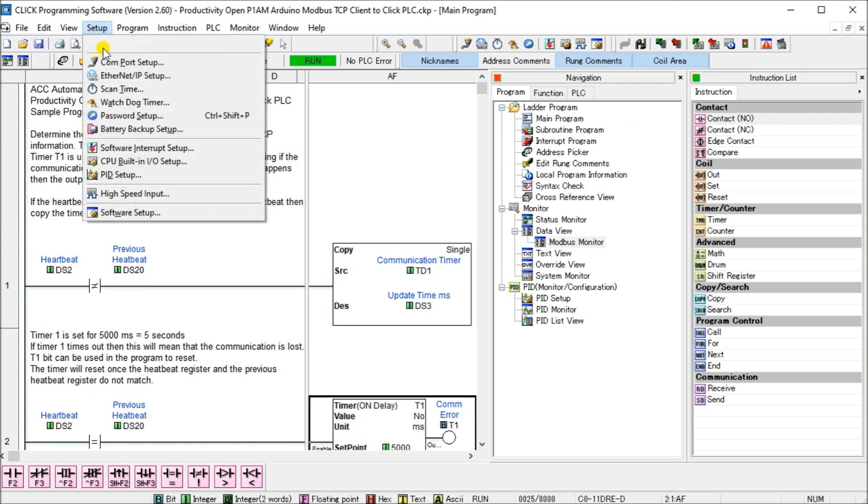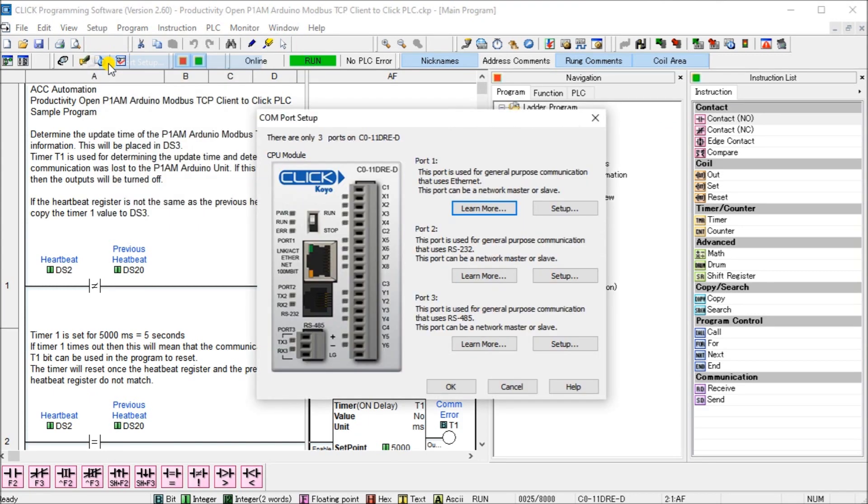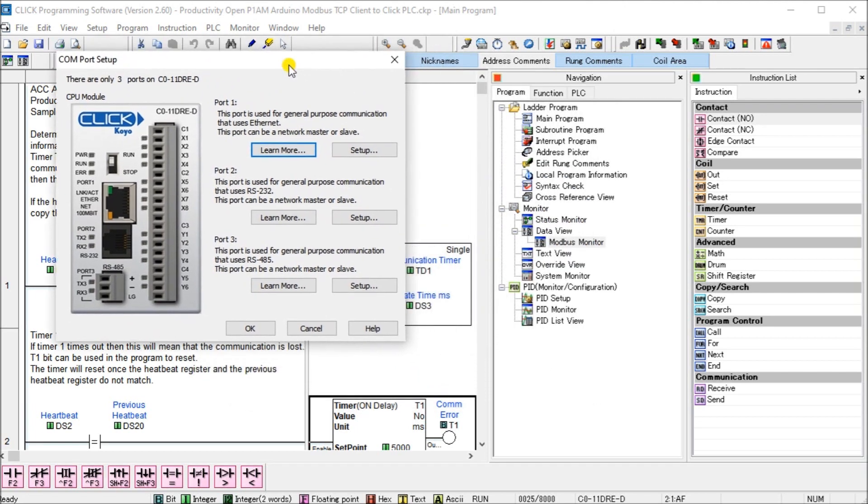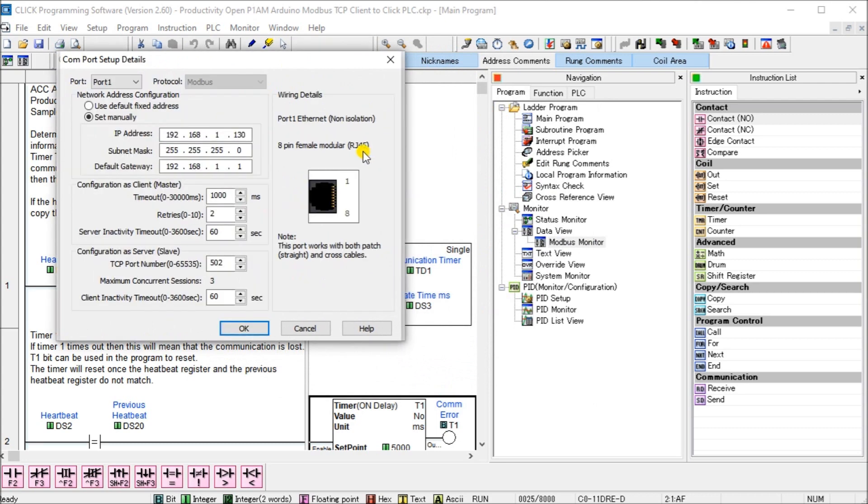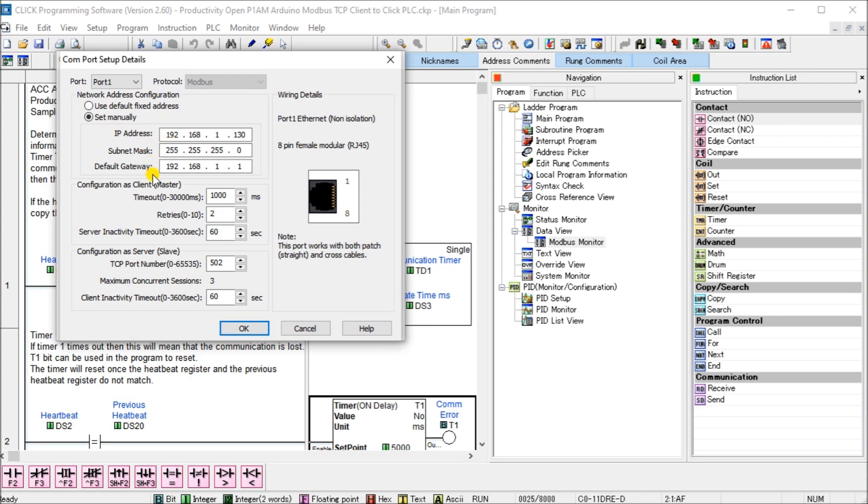If we go to setup and then COM port setup, you will see that under port number one, we will use that setup and we will ensure that this is set for a static IP or a manual set for our IP address. In our case here, we're going to set for 192.168.1.130 with a subnet mask and our default gateway.